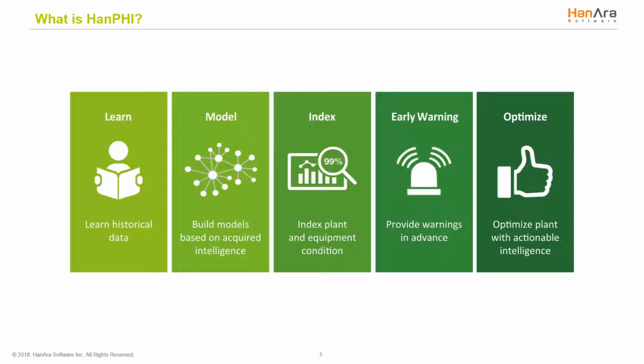HanPHI uses an empirical data model that learns historical fault-free normal operation data to create patterns. This solution identifies small deviations in equipment and operation behavior that are precursors to potential and/or hidden failures. The predictive data model uses data collected and stored by the historian.